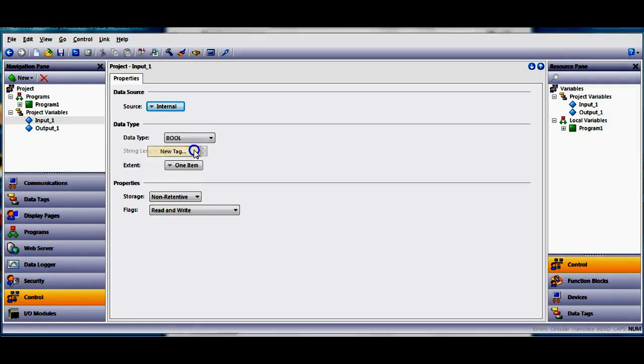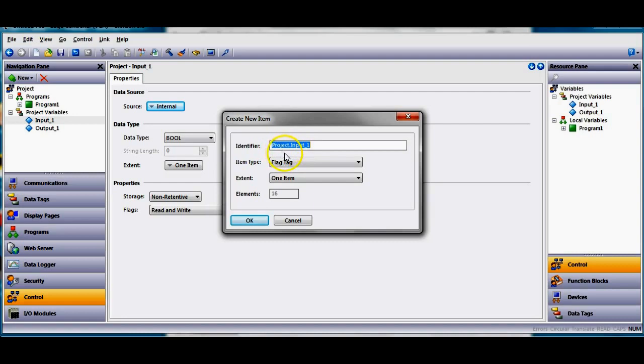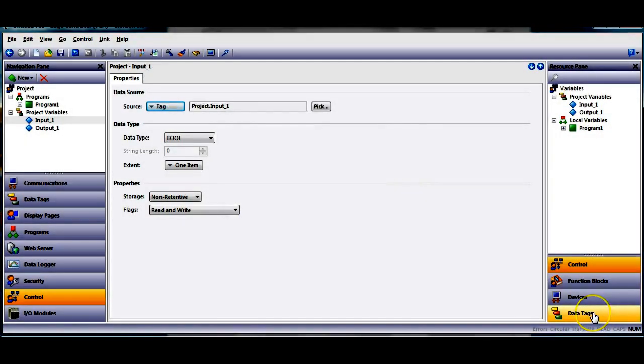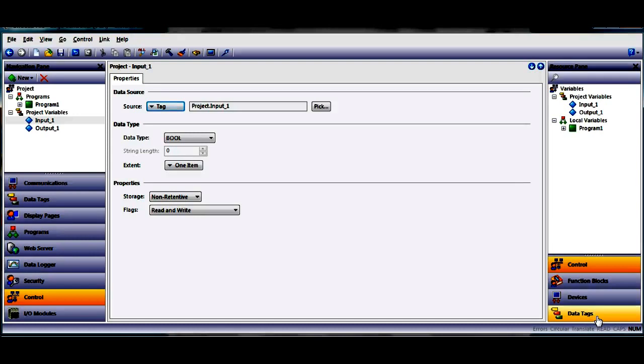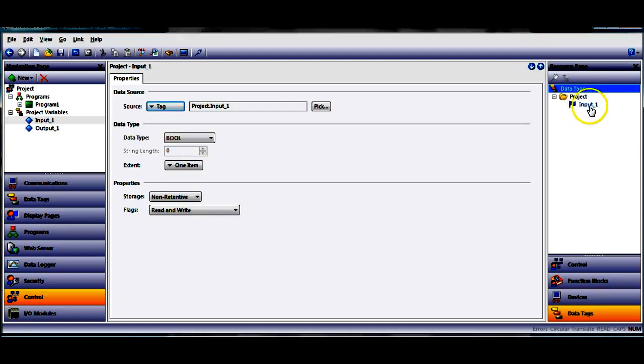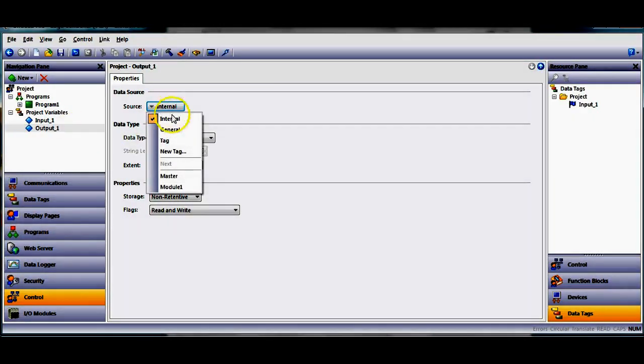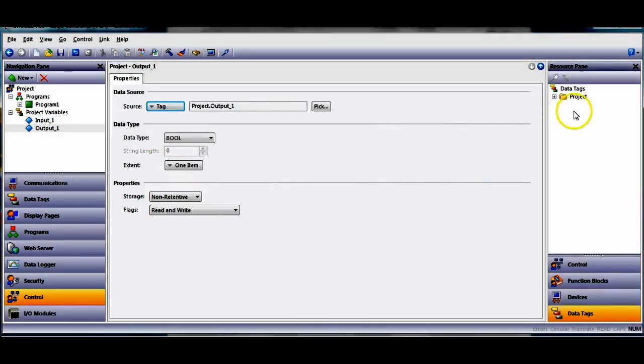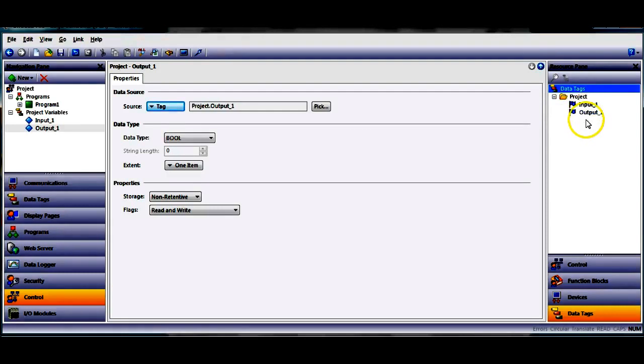Watch what happens when I do this. I'm gonna click on new tag, it's gonna say hey I could not identify this out in the HMI environment, do you want to declare a new tag and I want you to notice folks that there's an identifier project dot input one. I'm gonna go ahead and flag tags correct, click okay, boom. So now when it's done I go over here to the lower right hand corner, look I now have a category called project here and then in there I've input one. Let me go ahead and add this output one, I'm gonna go ahead and hit the new pull back create a new tag once again say yes and over here now it should show up, look it sure did.